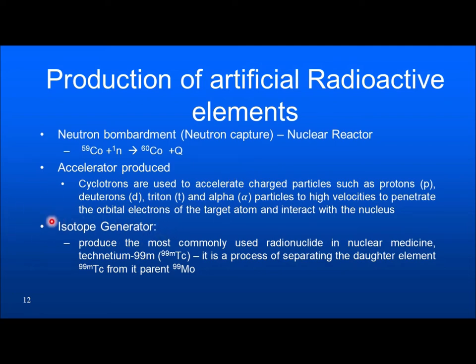The third method is the isotope generator. This is because some radioisotopes used in medicine, like technetium-99m, have very short half-lives — about six hours. Because of the short half-life, they cannot be transported as such. So they transport the parent element, molybdenum, and the daughter element technetium is in equilibrium, decaying with the half-life of the parent. The molybdenum is transported to the hospital where technetium is extracted in a generator called the isotope generator.